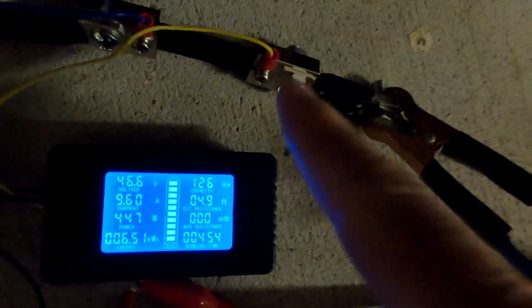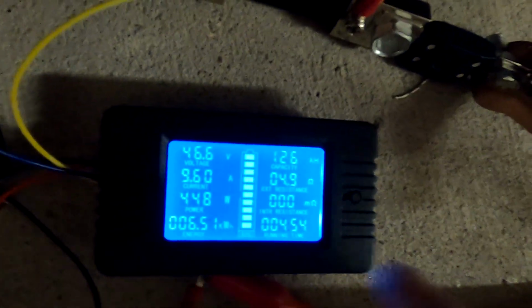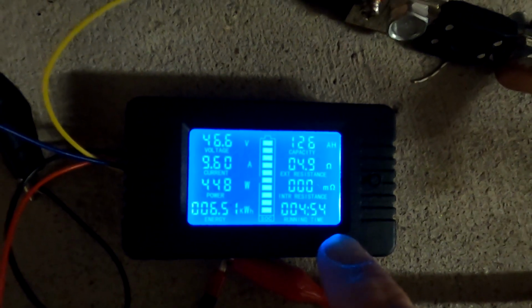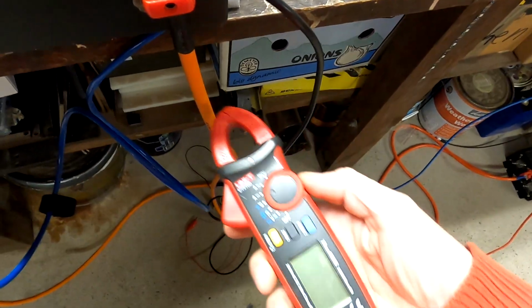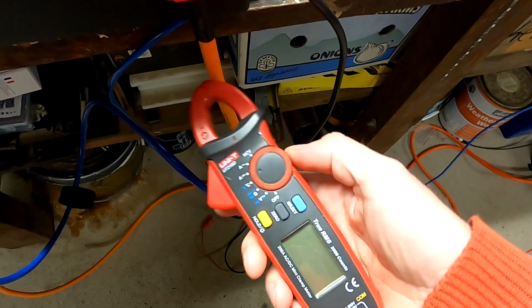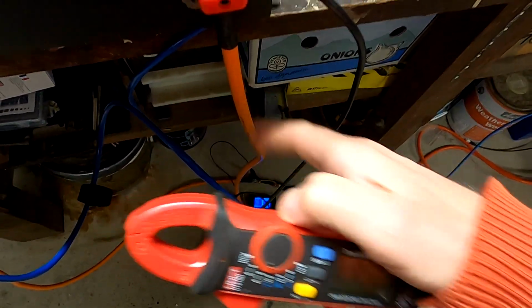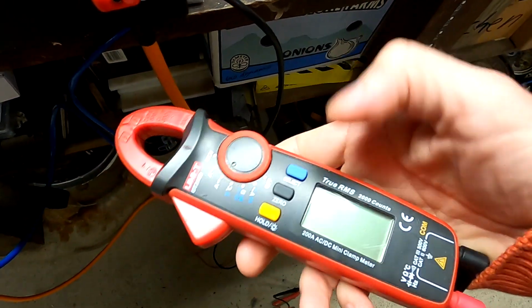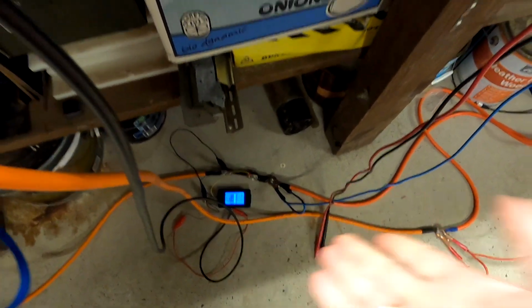It is a SEPLOS MASON 6.9, so it's supposed to have 6.9 kilowatt hours, but we could pull 6.5 with this shunt tester, within 4 hours and 54 minutes. But we know the current measurement we measured with a clamp meter directly on the cable was about 1 amp off. This one showed 1 amp more than the actual shunt tester for some reason. I think this has to do with the DC ripple again and how the shunt tester measures.